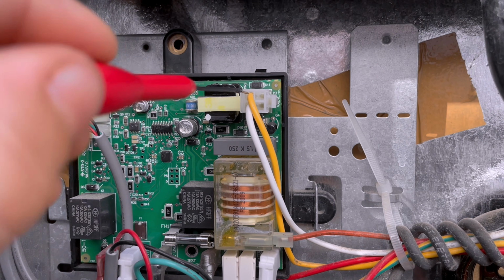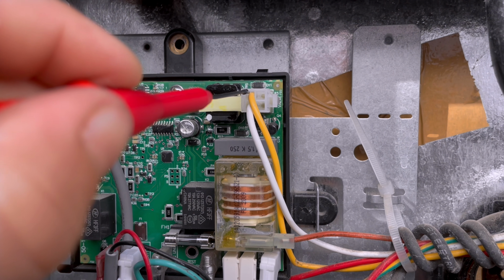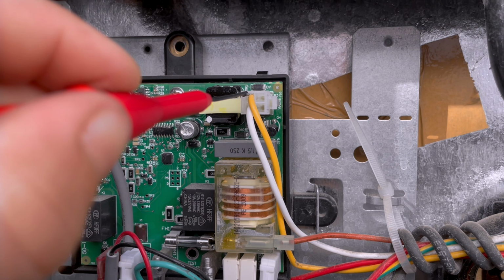Very exciting. If you do not hear a click, check for 12 volts here to see if we're sending 12 volts to the gas valves. If the gas valves are getting 12 volts but not clicking, there's a good chance the gas valve is your problem. If you hear a click but no tick, tick, tick, tick, tick, then the igniter is our problem.